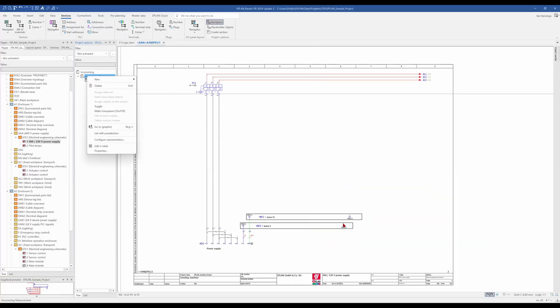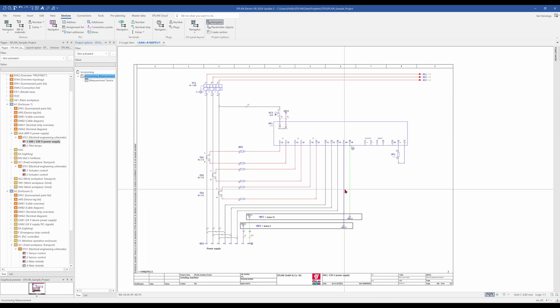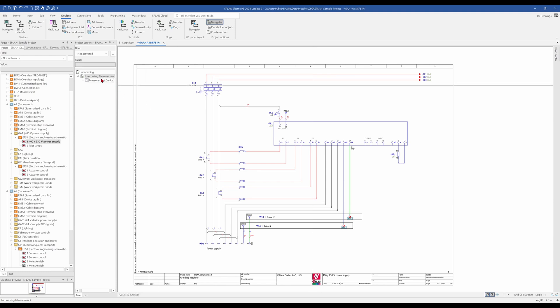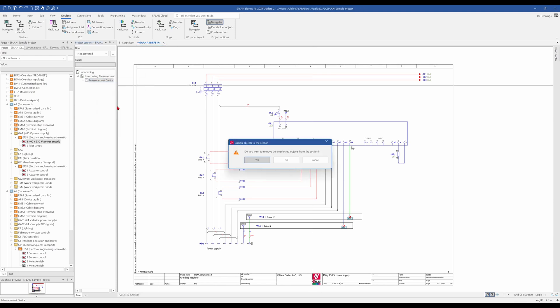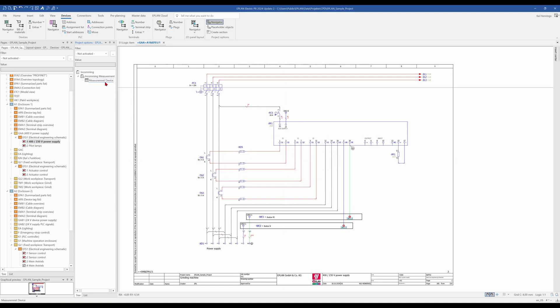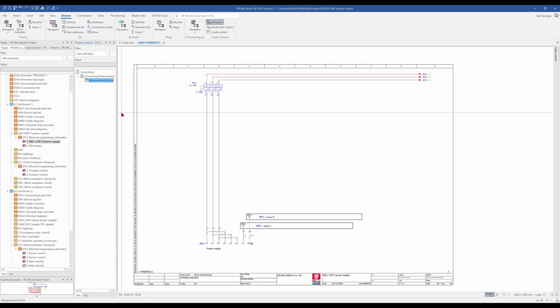So you can see that we have forgotten here some connections to the busbar. So we mark these two connections here, and make right-click, assign object to the section. Then you get a question, do you want to remove the unselected objects from the section? We say no, because we want to keep everything and add only these two connection points here. And when we toggle now, it works.